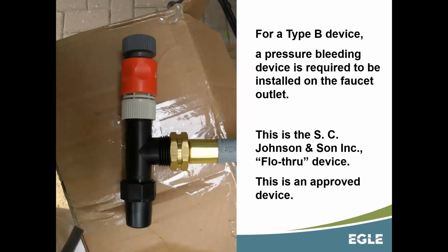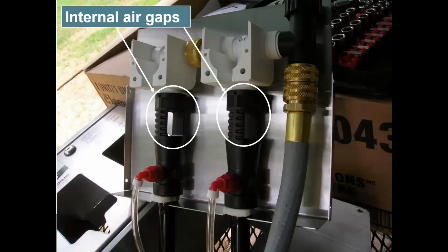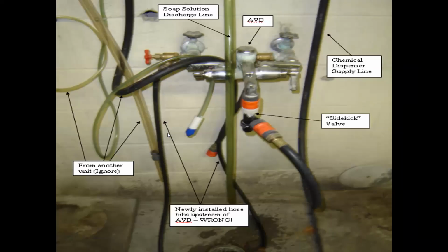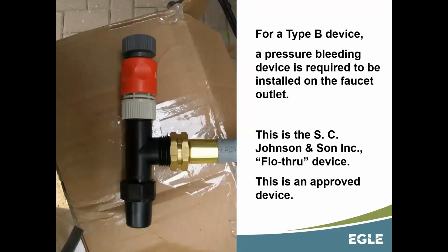This is an example of one of those devices. And the reason that this is necessary is because, if you recall this picture that we had here, when this is attached to the faucet, it has this atmospheric vacuum breaker on it. Normally, this cannot have a valve downstream of it. So you need this bleed through device to avoid having that problem of a valve that is shutting things off and creating that back pressure.